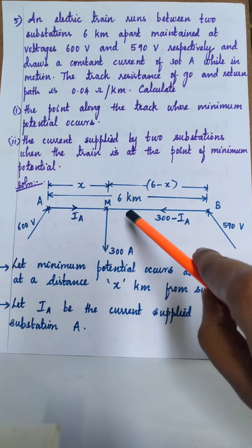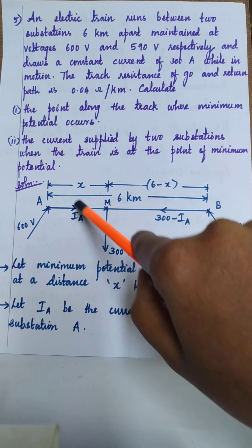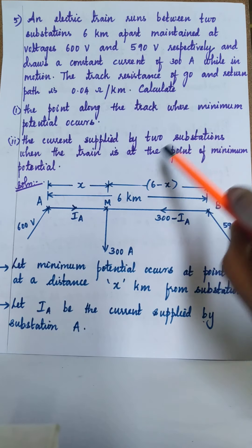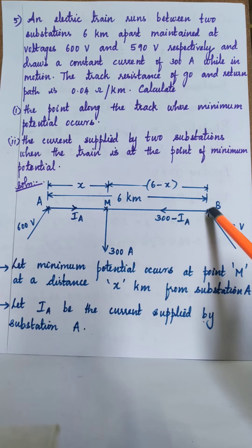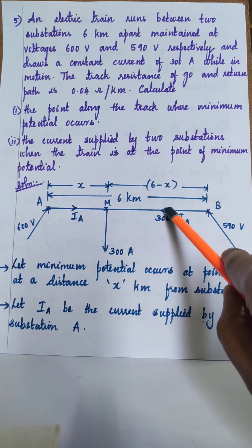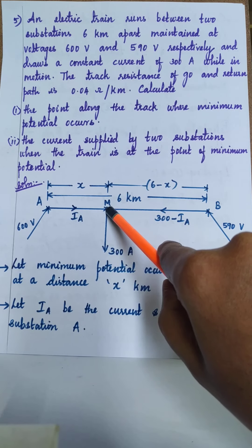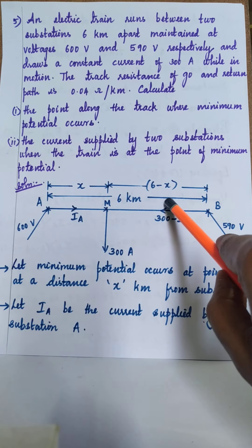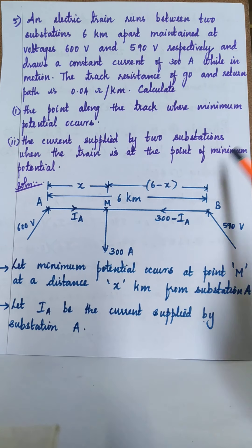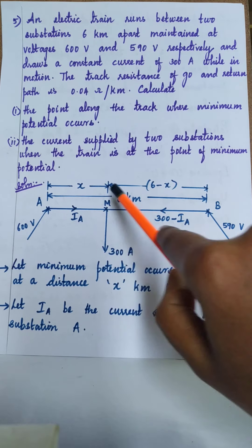The train draws a constant current of 300 amperes, so at point M it also draws 300 amperes. Let Ia be the current supplied by substation A, so 300 minus Ia will be the current supplied by substation B. The current direction from B is taken as 300 minus Ia — if taken along the other direction it would be Ia minus 300, but since it is current supplied from B, we use 300 minus Ia.